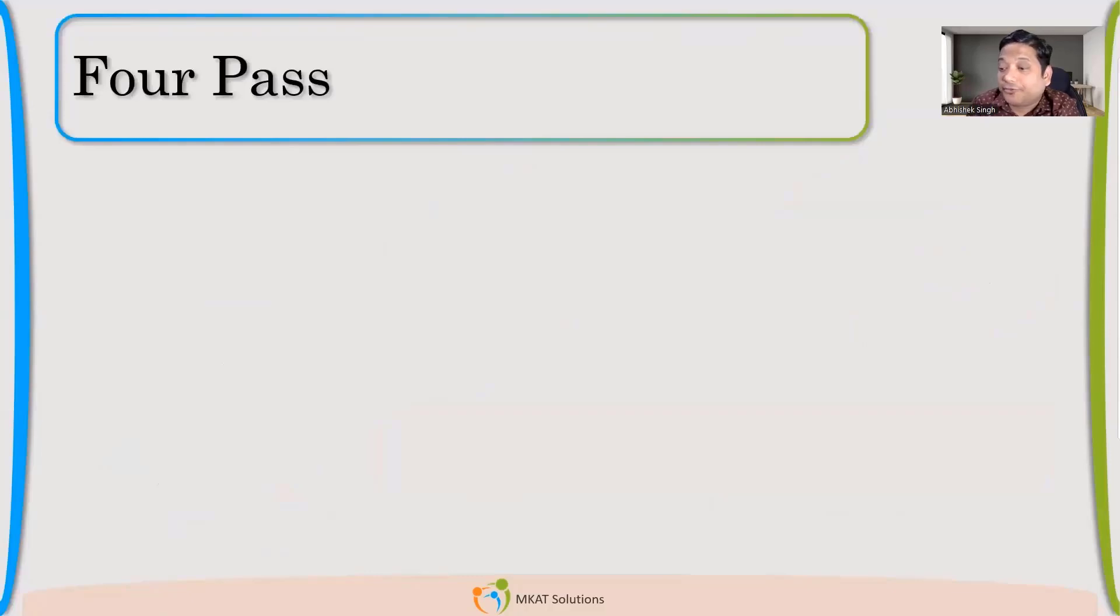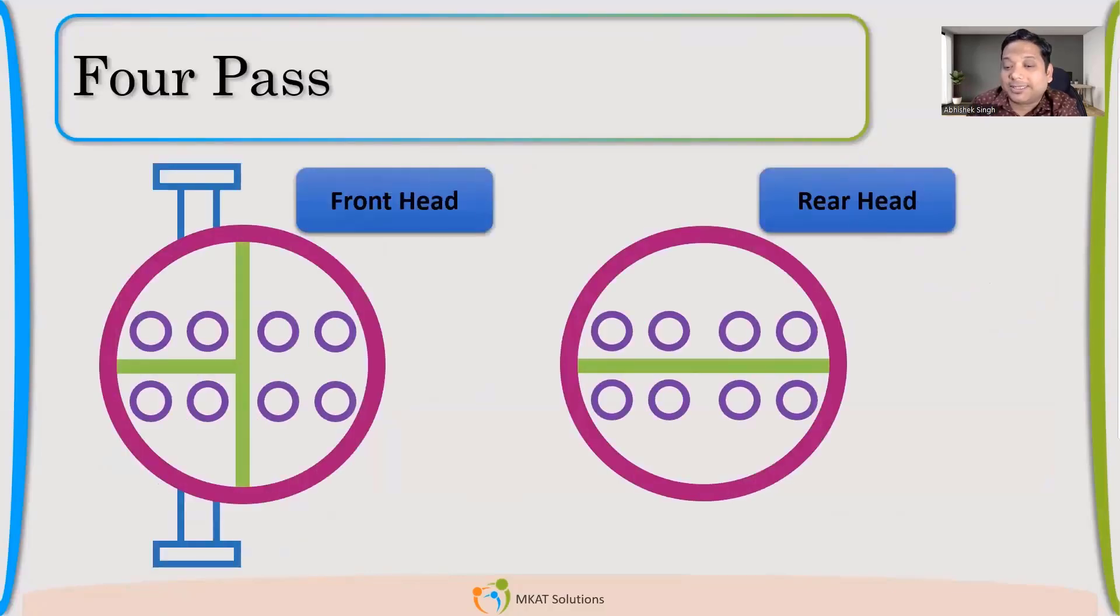Now, what about four pass? If I have a four pass heat exchanger. How the division I'll make in the tube sheet. There is front tube sheet and rear end tube sheet. You can see the flow is coming like this, entering in the two tubes, which are available because of partition plate, other tubes are not available for the inlet. So all flow will enter in these two tubes. It will come out from these tubes on the other side of tube sheet. So one pass happened.